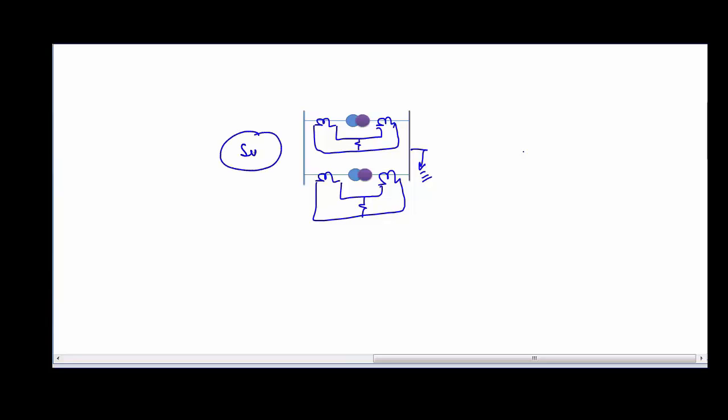Now similarly, let us suppose that there was a fault on the bus bar itself. So suppose that there is a fault at this point, then it's obvious that we have CTs connected in this way, and here we have CTs connected in this way, and we have a differential relay, and we have a system at this point which is going to feed the fault.